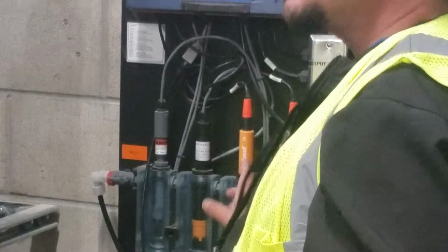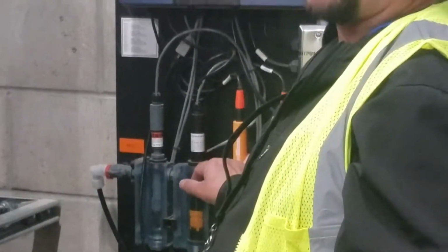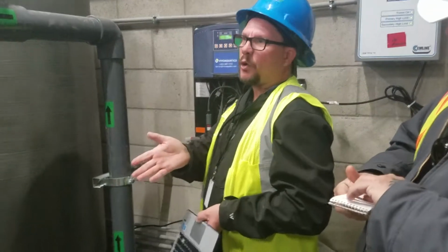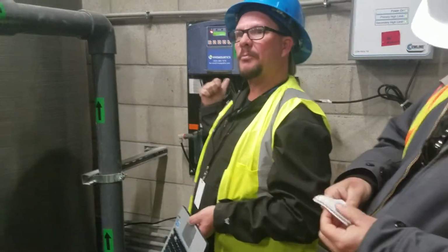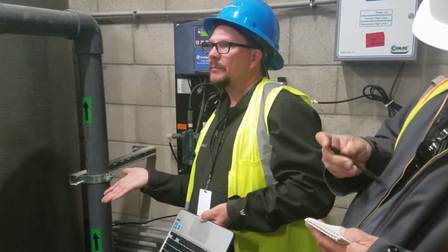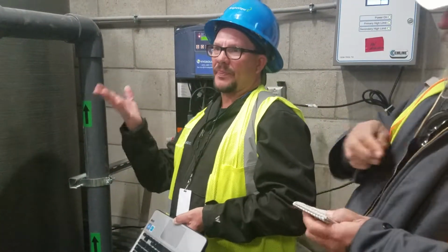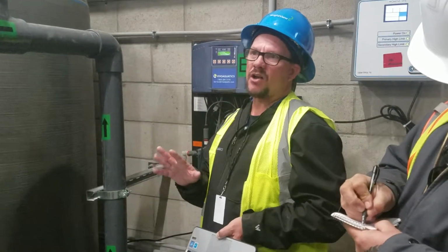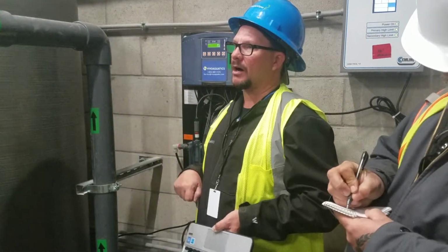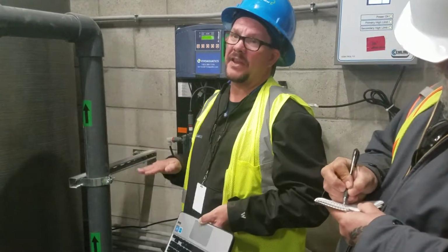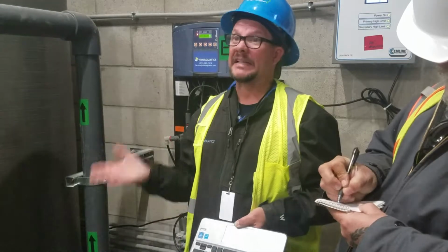It's telling you that you've got a low pH, or that pH has either run too long, or it came out of its set point, and it showed an alarm parameter. Doesn't necessarily mean that it'll turn off. It depends on what the level of alarm is. If it's going to lock out, a lockout alarm will be a runtime error, a runtime limit, for obvious reasons. That means you don't want it to feed until somebody comes over here and corrects it.